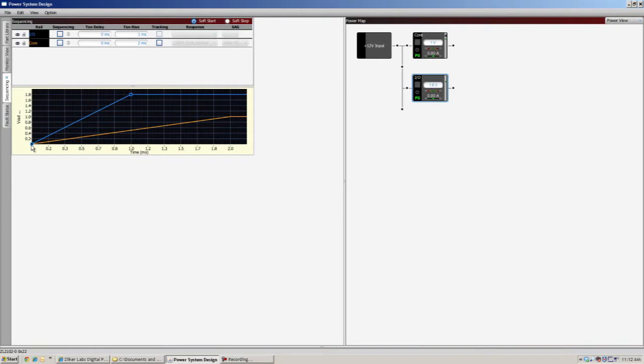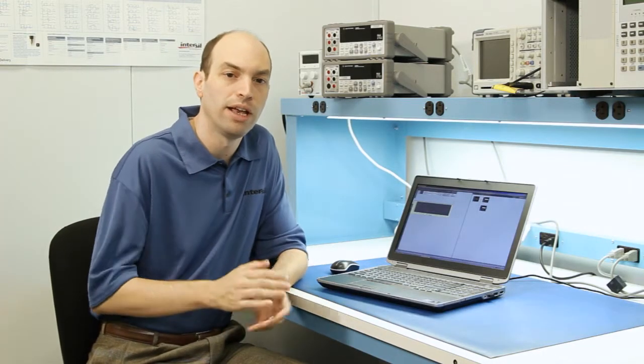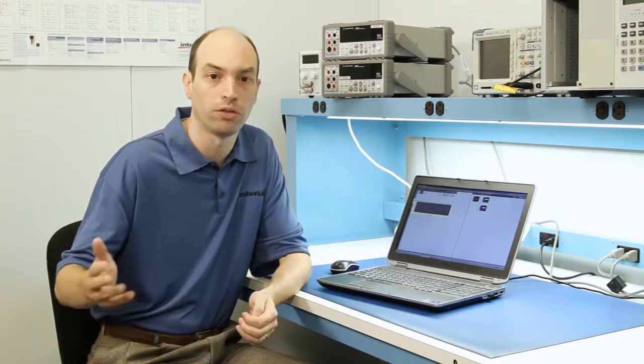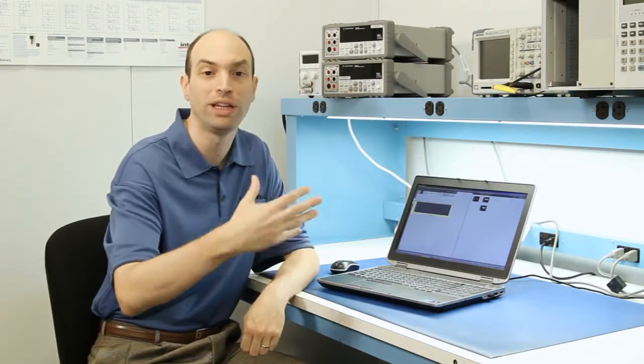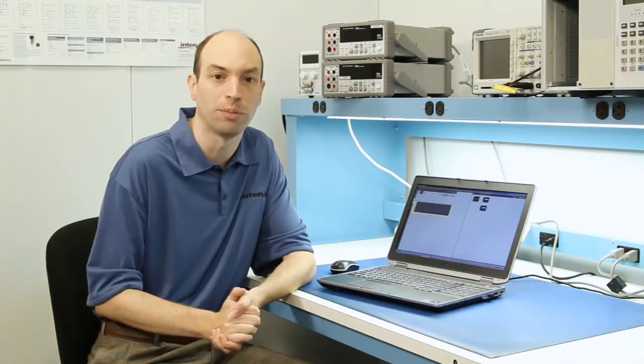The ones at the beginning set up the T on delay. The T on delay is the amount of delay that you get from the enable signal to when the device starts ramping. So if you have multiple devices and you have one enable going through the entire system, you can then set up a time-based sequencing standpoint.